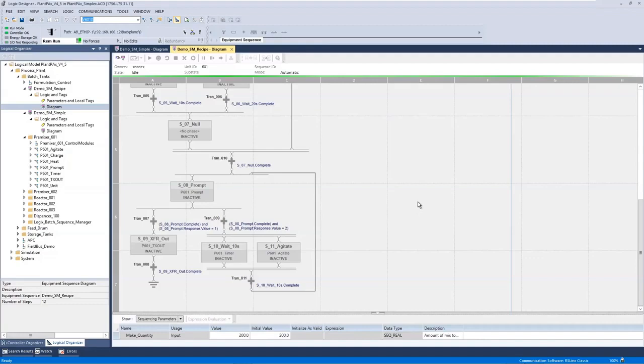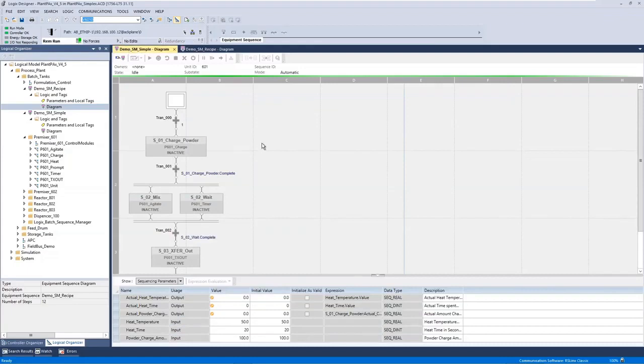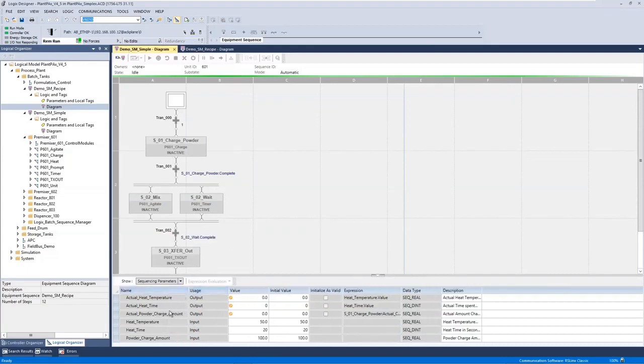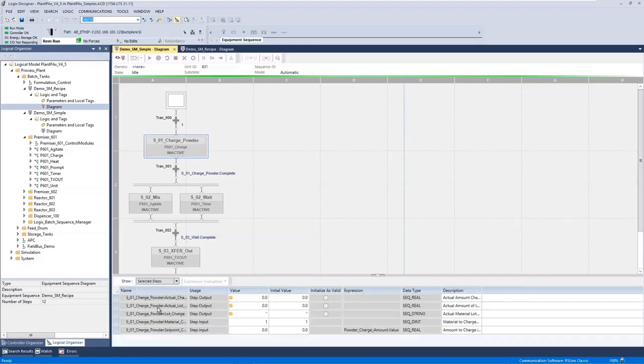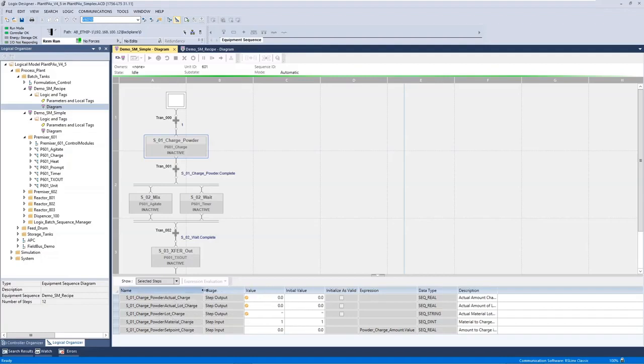These sequences can have recipe values that you can specify. In this example you can see we've specified one value that we'd like the user to specify when starting the recipe, and the make quantity. On our simple recipe we have three values: the heat temperature, the heat time, and the amount of powder to charge. For each step you can then either use these recipe values or directly code a value.